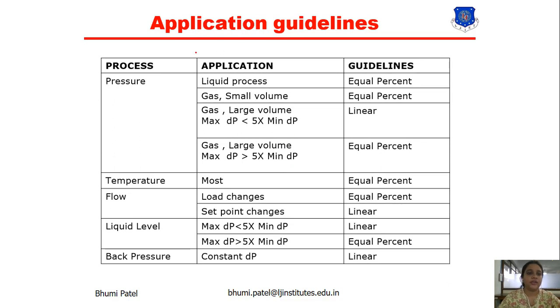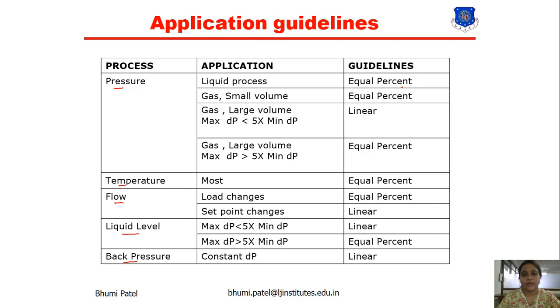Here you can see that we have different processes used in instrumentation — for example, pressure, temperature, flow, liquid level, and back pressure. For the pressure process, in a liquid process, the application guideline for valve characteristics is to use equal percentage. For gas with small volume in the same pressure process, we can also use equal percentage.